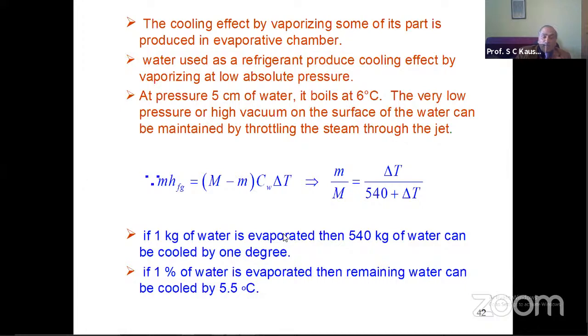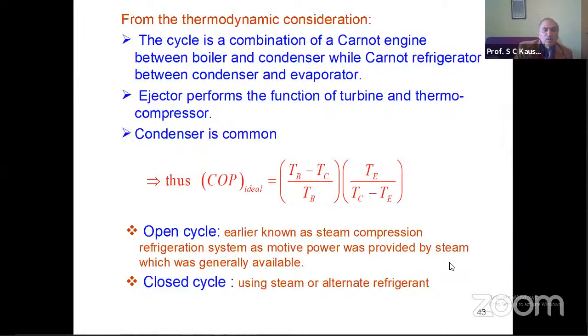Alternatively, if 1% of water is evaporated from the surface of the water, then the remaining water can be cooled by 5.5 degrees centigrade. It is based on this principle that the ejector refrigeration system works in the evaporative cooling chamber. So this system is simple in design and viable. The overall COP is also high because the input heat source temperature can be increased, and the common condenser or sink temperature can be used for the ejector cooling system.